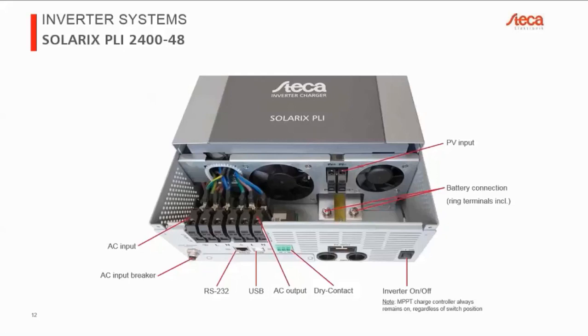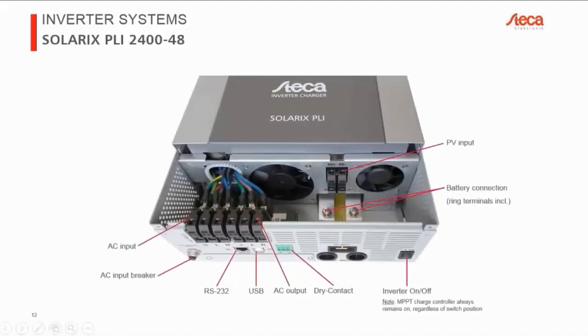And during the day, as soon as you have enough PV voltage on the PV input, which is here, the device will automatically start up, start the display, start the charge controller, but the actual inverter portion will remain off. And then finally, we have the battery connection here. The ring terminals are already included in the package of the SOLARIX PLI. The recommended cable cross-section for this is 35 to 50 millimeters square.